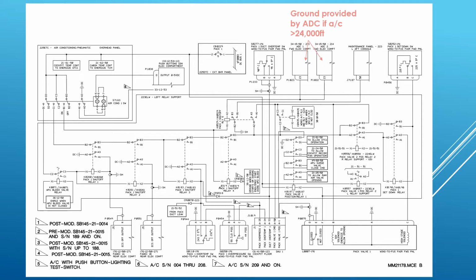Now the high stage solenoid, again, you'll have to trace this through yourself, but what we said with the high stage valve is if the other pack's not working, so in this case this is pack 1, so if pack 2 is not working, the high stage solenoid will energize. So we've got, it says pack valve 2 position relay number 2, just on the right hand side of the picture there, about halfway in the middle of the screen, slightly to the right. It's shown in the de-energized state. So this is the position it's in if pack number 2 was not working. And basically if you trace it, it allows electrical power to come down to the high stage solenoid, causing it to energize. But if pack 2 was online, it would stop that from happening.